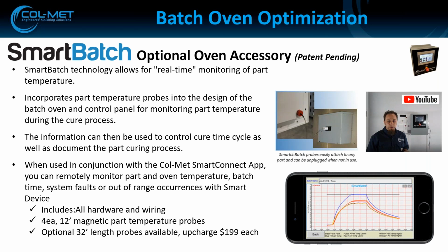All of the temperatures are also recorded. Every 60 seconds, it takes a snapshot and stores that in the touchscreen. Then you can take that data and export it with the USB port that's on the screen, or you could also have it emailed with our Smart Connect app. Every time the batch is complete, it'll send out a little email showing you the temperature and time report. The system comes with the wiring and the junction box and the plug and everything. And you can also purchase additional 32-foot extension cables if you need to get further into the oven.